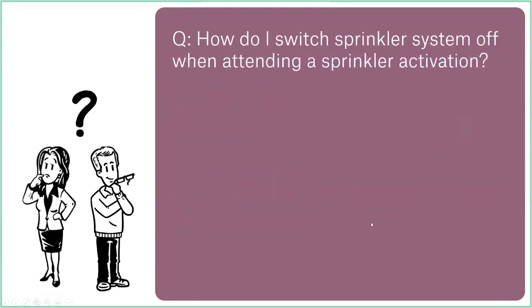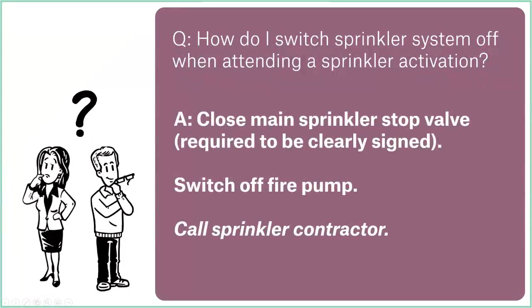Okay, next question. How do I switch a sprinkler system off when attending a sprinkler activation? Well, really, all you need to do is close the main sprinkler stop valve. And this should be clearly signed. So actually in the British Standard itself, there are instructions on where the sign should be located, what colour it is, what size it is, what size each of the letters are. It should be clearly marked in terms of where the stop valve is.